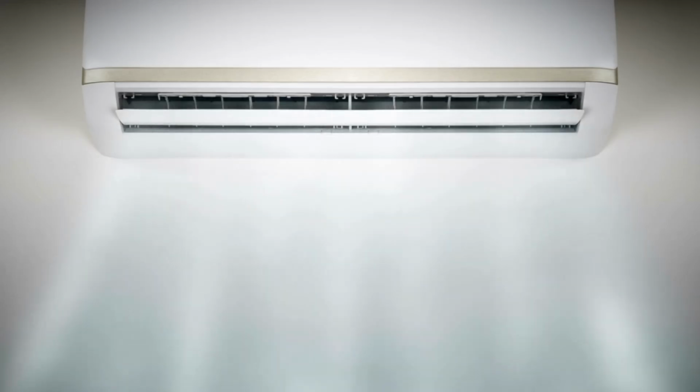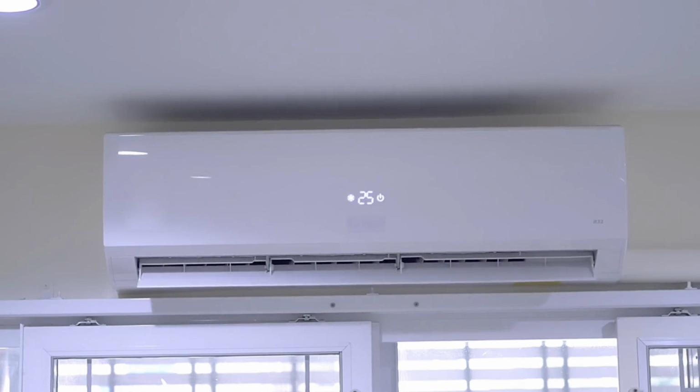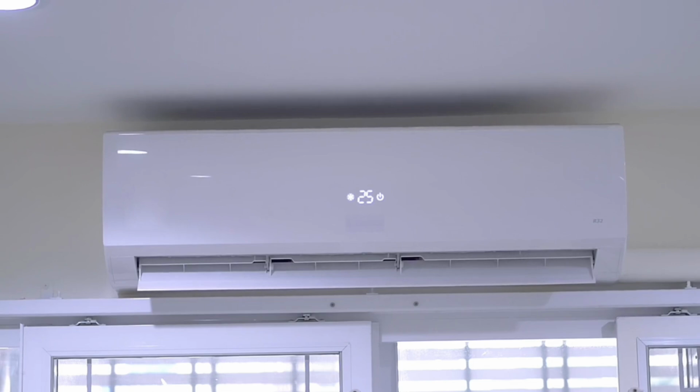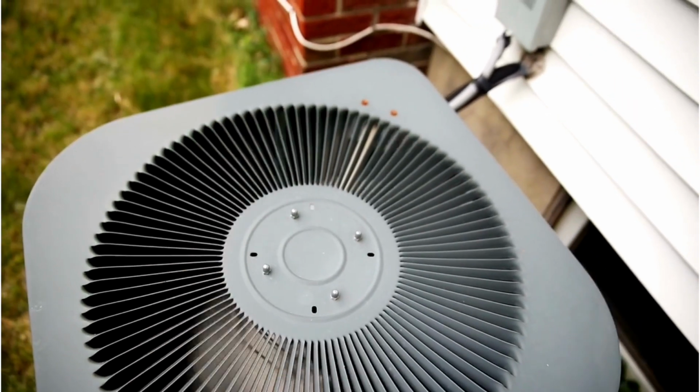So, 1 ton of cooling is the amount of heat energy that would melt 2,000 pounds (907 kilograms) of ice in a day. In modern terms, 1 ton of cooling capacity equals the ability to remove 12,000 BTUs (British thermal units) per hour. A BTU is the amount of heat required to raise the temperature of 1 pound of water by 1 degree Fahrenheit. So, when an air conditioner is rated at 1 ton, it means it can remove 12,000 BTUs of heat from a space in 1 hour.